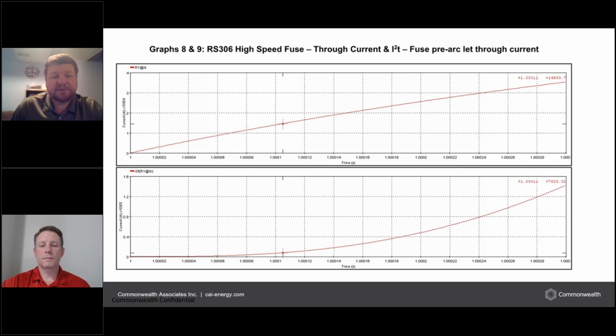And once we model this, we can take the fast-acting fuses, these current limiting fuses in the DC system, and compare that DC rise to what the fuse itself is going to trip at based on the available energy through that fuse. And we see the race. And just like any race, one side's going to win, one side's going to lose.